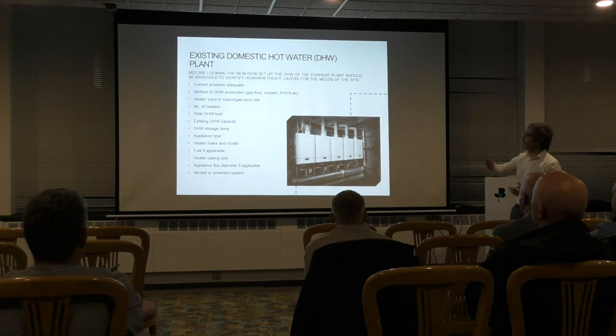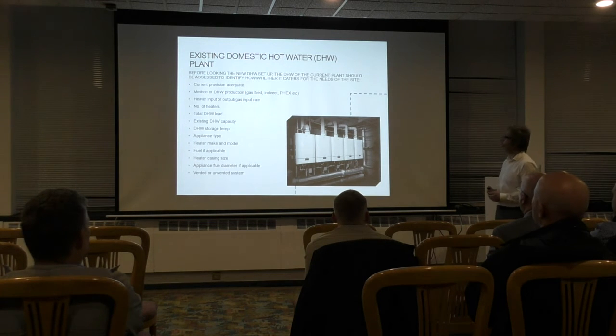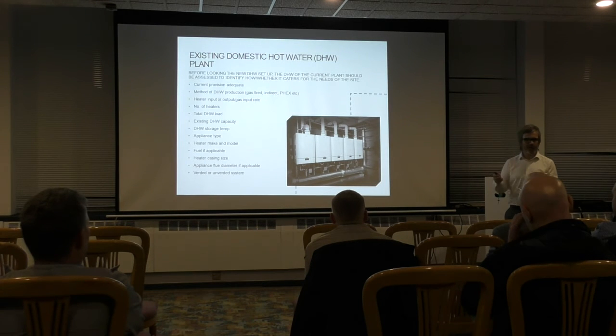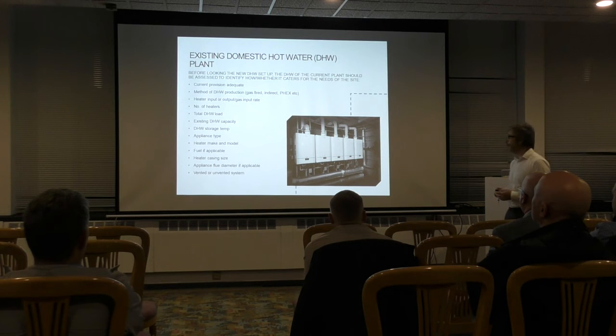But really, I suppose the first point there is: is the current provision adequate? Therefore, the first people to tell you that we're running out of hot water. But how are we producing the hot water? So direct fired gas water heaters, instantaneous plate heat exchangers, semi-instantaneous plate heat exchangers, that type of thing. But just a few other pointers there. Like I said, I won't go into that in too much detail. I'll just say we're a boiler manufacturer, not a water heating manufacturer.